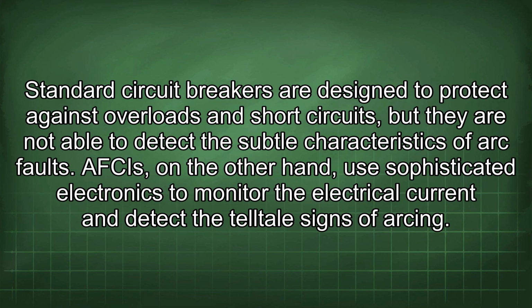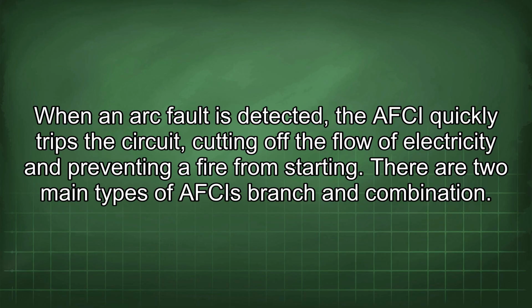Standard circuit breakers are designed to protect against overloads and short circuits, but they are not able to detect the subtle characteristics of arc faults. AFCIs, on the other hand, use sophisticated electronics to monitor the electrical current and detect the telltale signs of arcing. When an arc fault is detected, the AFCI quickly trips the circuit, cutting off the flow of electricity and preventing a fire from starting. There are two main types of AFCIs: branch and combination.